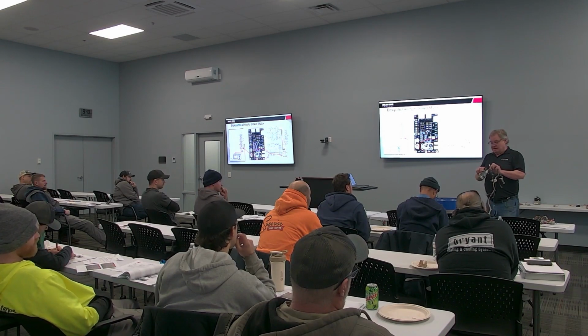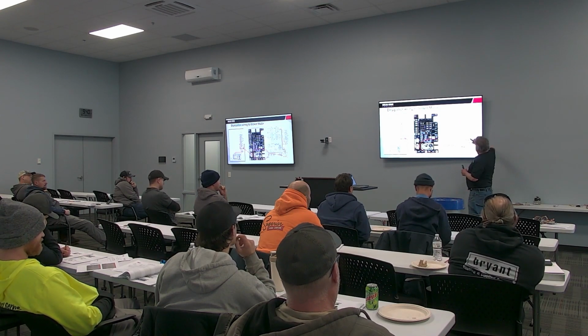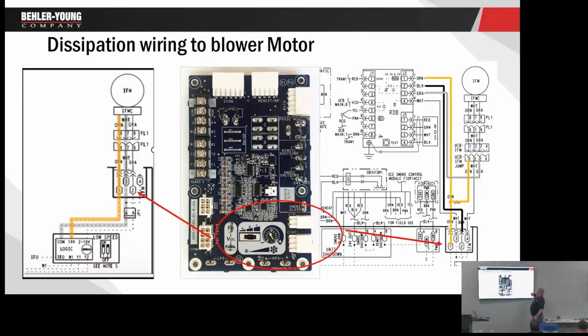So that's actually this board. So from this here, remember we had the gray and then the orange? We still have the orange, but now the gray is a black, which comes to the dissipation board, and then the gray comes here as well. So what happens is on a call, instead of a gray wire there, we're going to have a black wire. Same difference, 9 volts DC, whatever we should have. But if I have a leak, if I have to mitigate the leak, you can see what it'll do is it can now take the orange 10 volts DC, send it straight down the gray wire to bring the blower on. Make sense? Okay, just so you kind of see how it's going to be wired in. And you're going to say, well, Dave said there's a gray wire. There's not a gray wire, it's a black wire. Well, now we have this mitigation board.